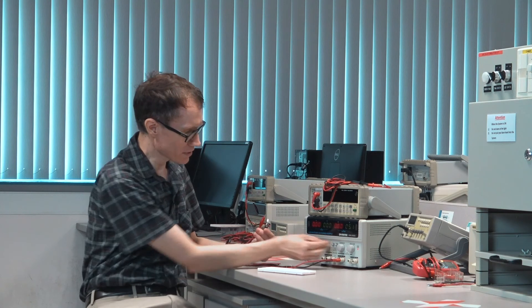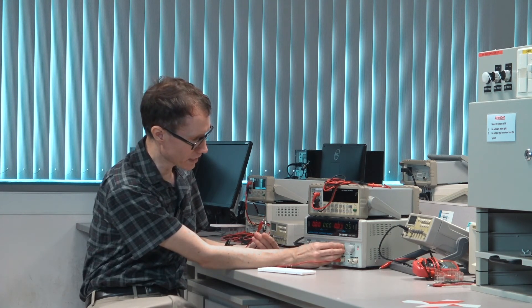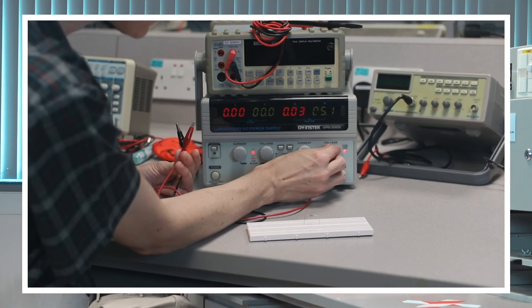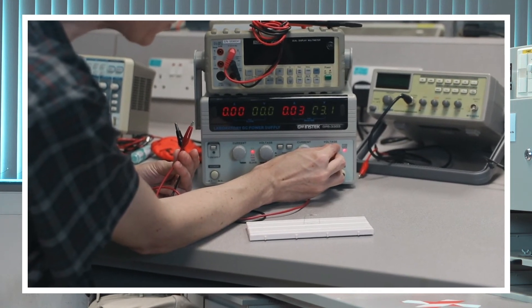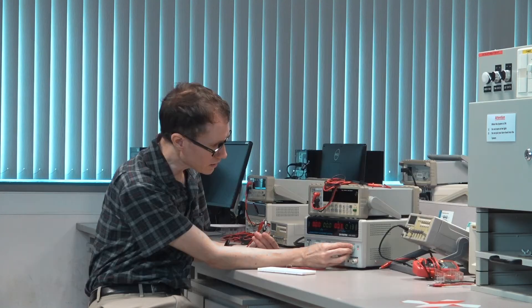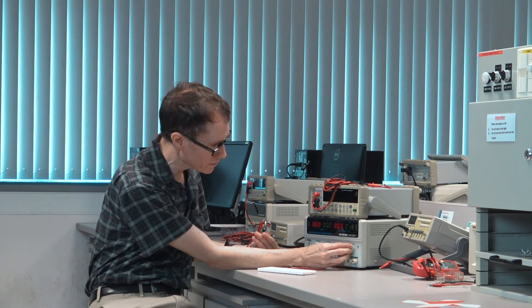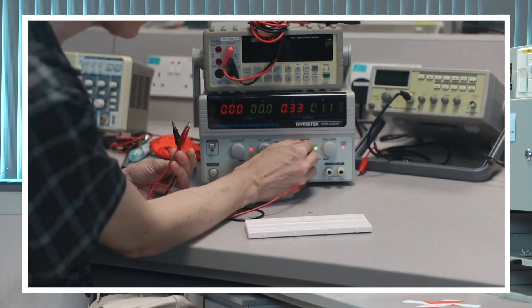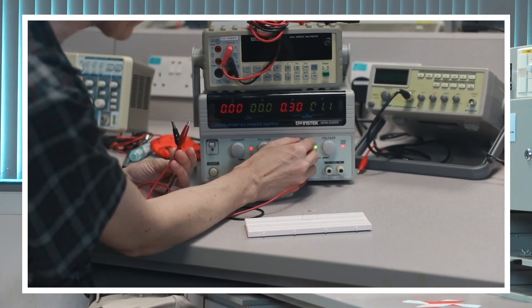Let's move the limit down and turn it off. So when the output is off, I should see some indication here of what the limit is. Let's set the starting voltage to 1 volt and let's set the limit also to, say, 0.3 ampere.